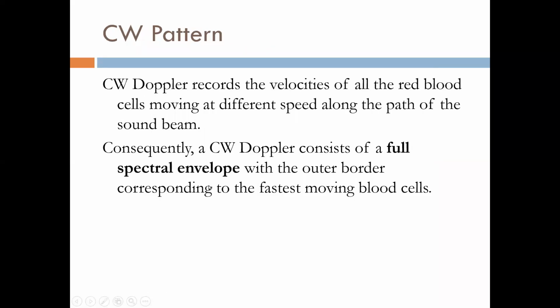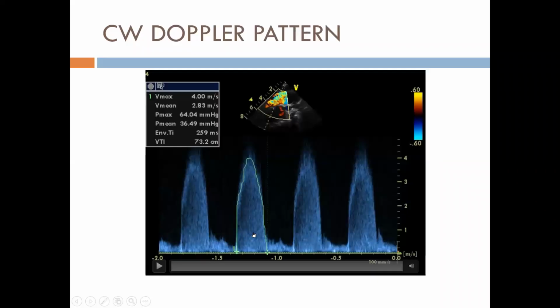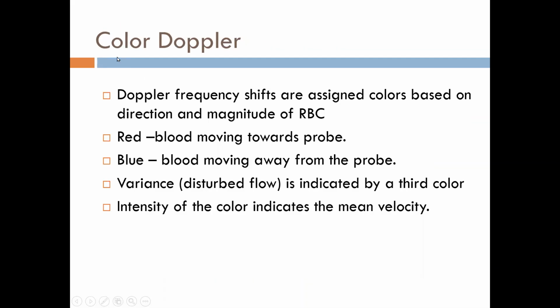But in case of continuous wave Doppler, what happens? You have a full spectral envelope. The blood with lesser velocity is also taken up. The blood with the highest velocity will be at the periphery. So you get the maximum velocity. So to get the highest velocity, you need to have a continuous wave Doppler.